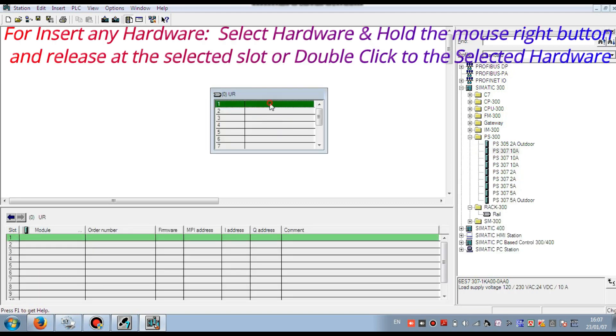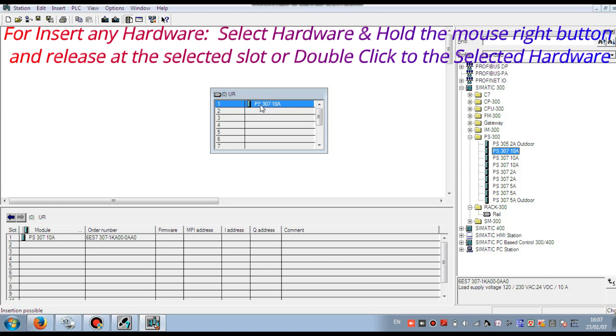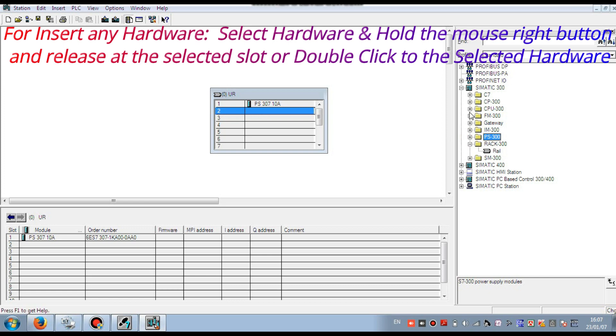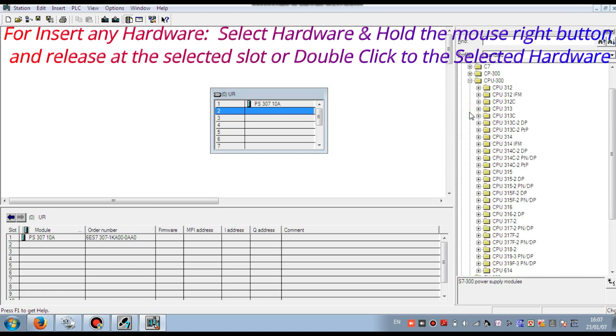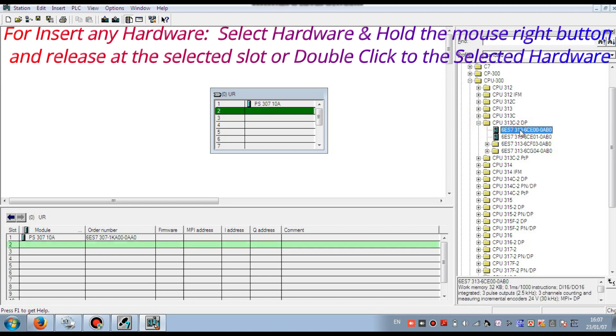Then we select the slot. The first slot must be the power supply. So we insert the power supply in the first slot. In the second slot we insert the CPU, because the sequence is: power supply, then CPU, then the other input/output cards.